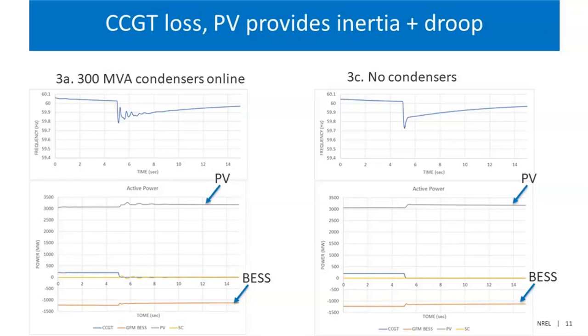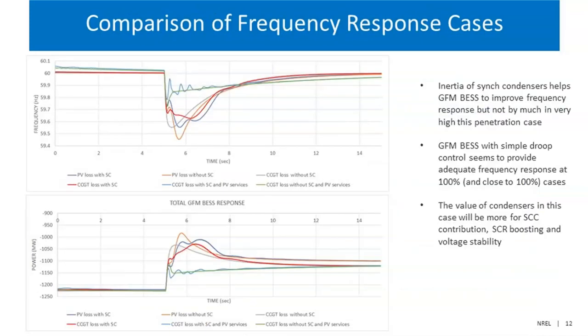But you probably can see these oscillations in the synchronous condenser case. And that's kind of echoing the things that other presenters were talking about, that there may be some control interactions between condensers and grid forming and other inverter-based resources. In this case, it's damped and the system recovers, but there might be situations that we didn't model, where this can become a stability issue.